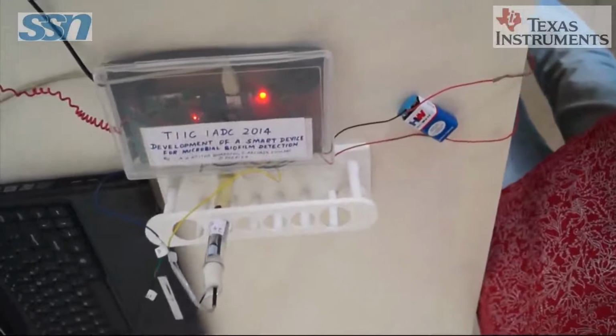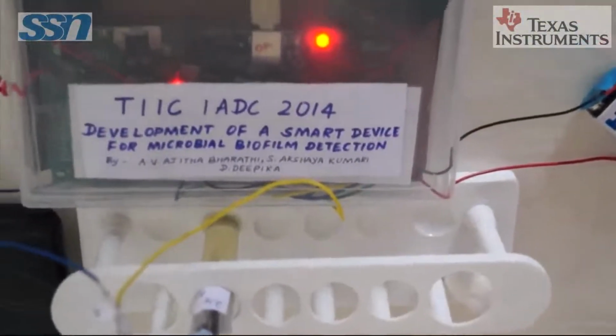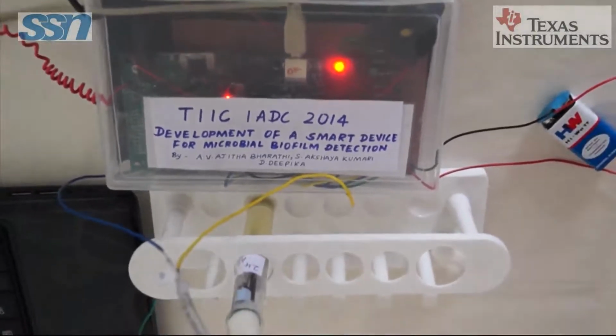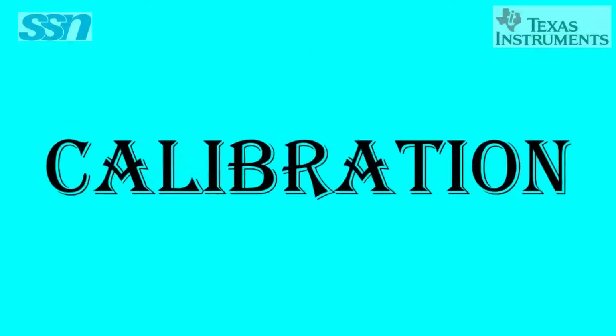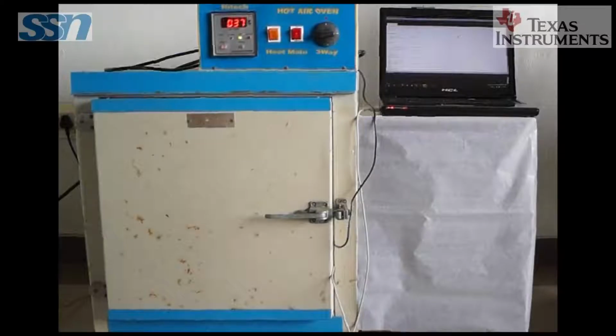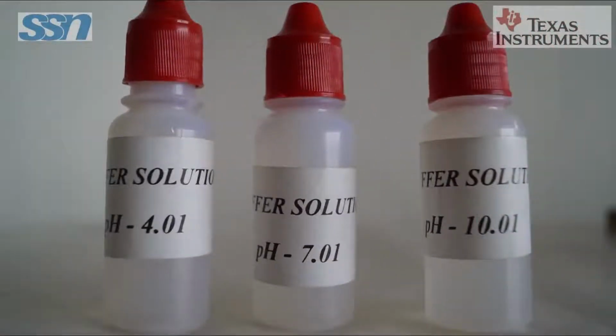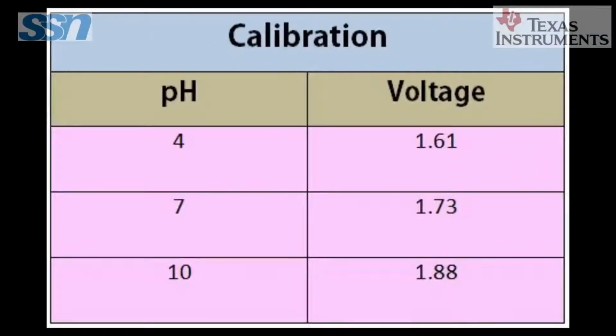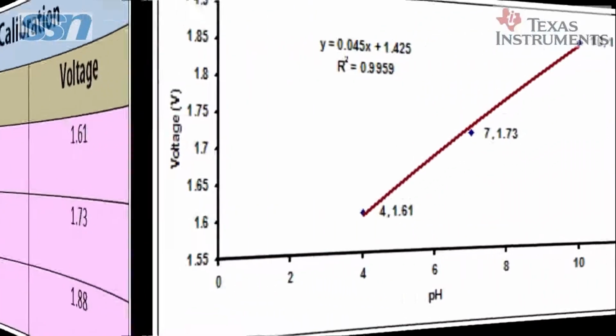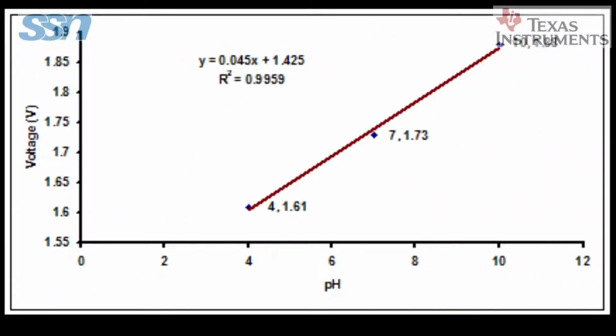The entire setup is placed inside the incubator to nurture bacteria at constant temperature. The entire closed device is placed inside the incubator and maintained at 37 degrees Celsius. Voltages of standard buffer solutions with pH 4, 7 and 10 are measured and taken as reference for calibration. Using these values, a linear line is established and the equation of a straight line is obtained. This equation is used to convert the obtained voltage values to the corresponding pH.